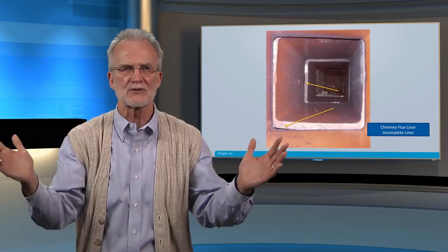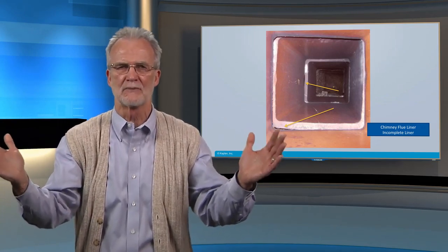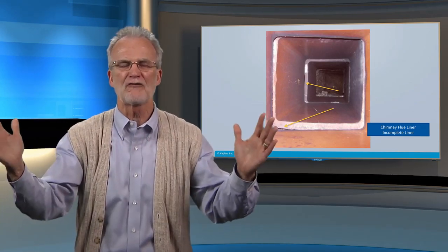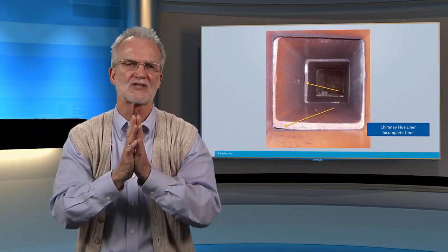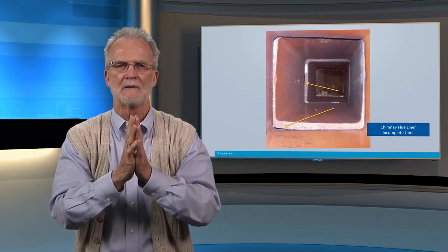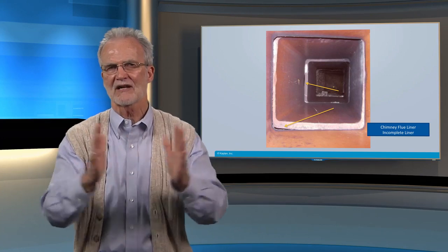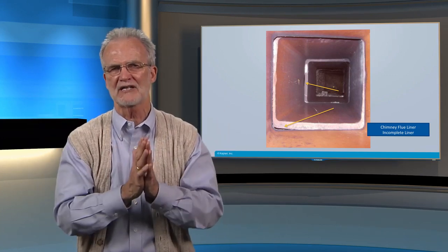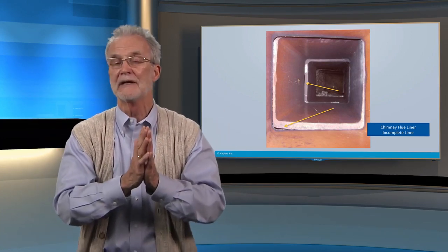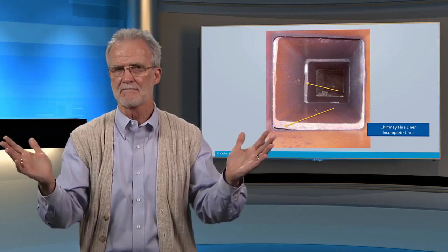Example, 70% of the flue is not visible to me. Sooty flue tiles, unable to see the tiles themselves. Make sure again that the customer is aware of the limitations to your seeing that flue, if that applies.